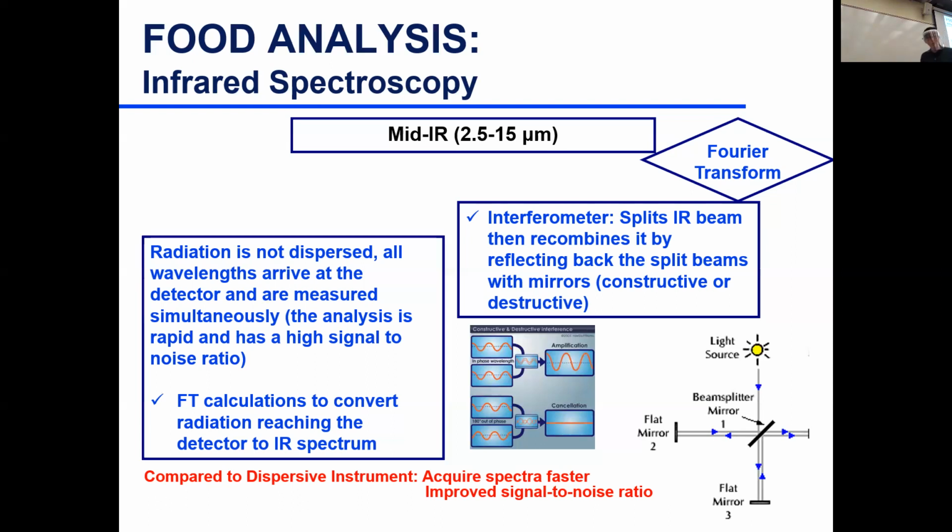The reason they do that is that sometimes you want to reduce the interference from compounds you don't care for, so you suppress certain wavelengths, and you want to amplify the energy that comes from particular wavelengths that you're interested in for that particular sample. So the way it's constructed is just based on positioning mirrors within the spectrophotometer to cause amplification or cancellation.